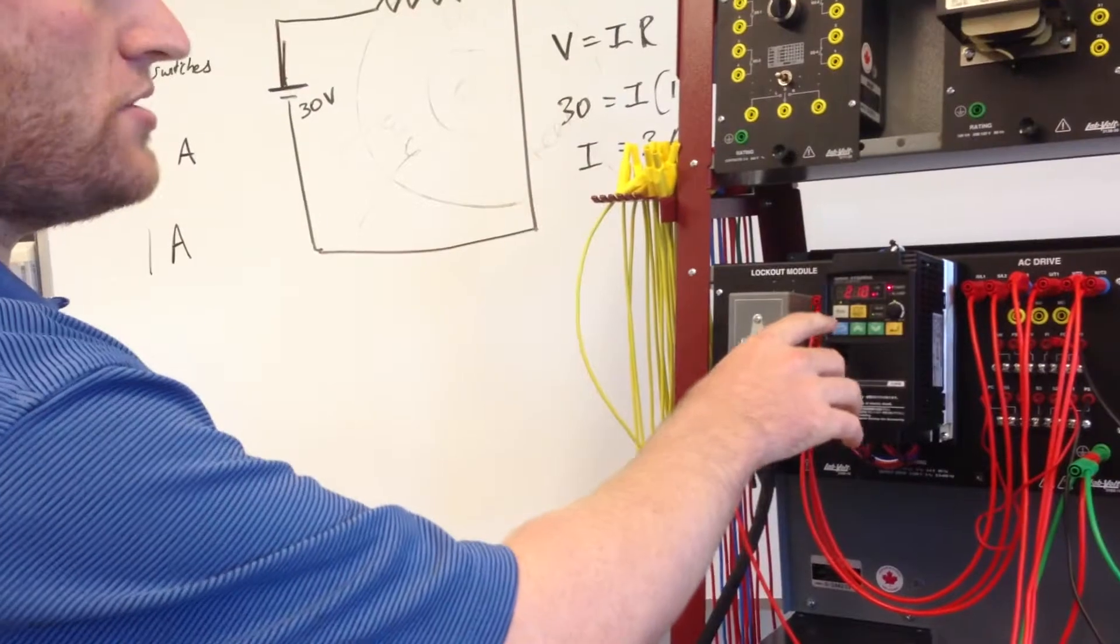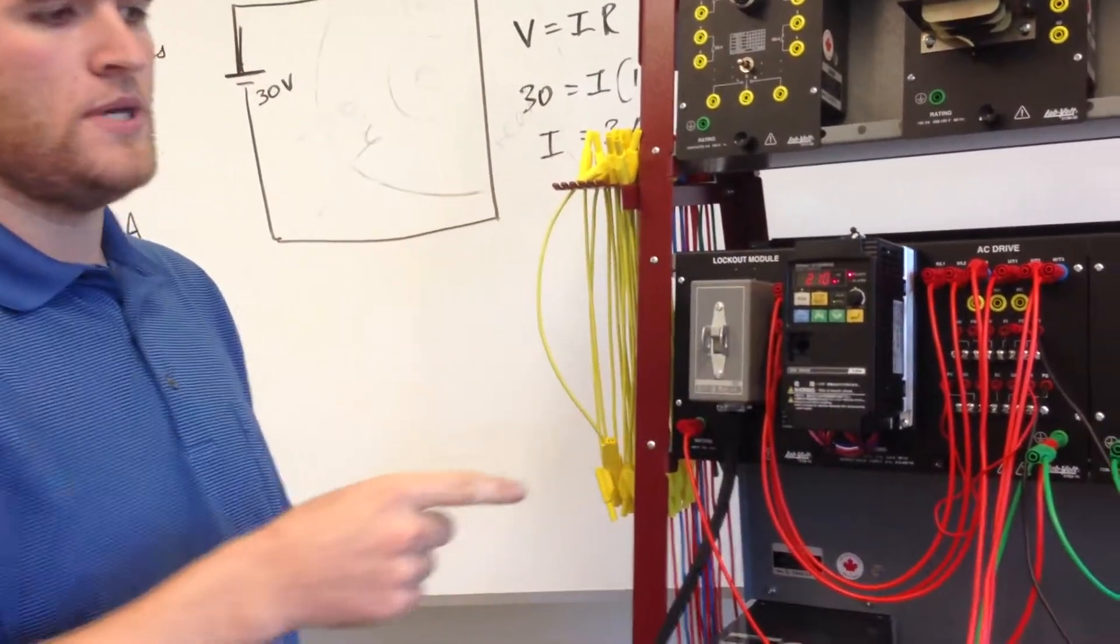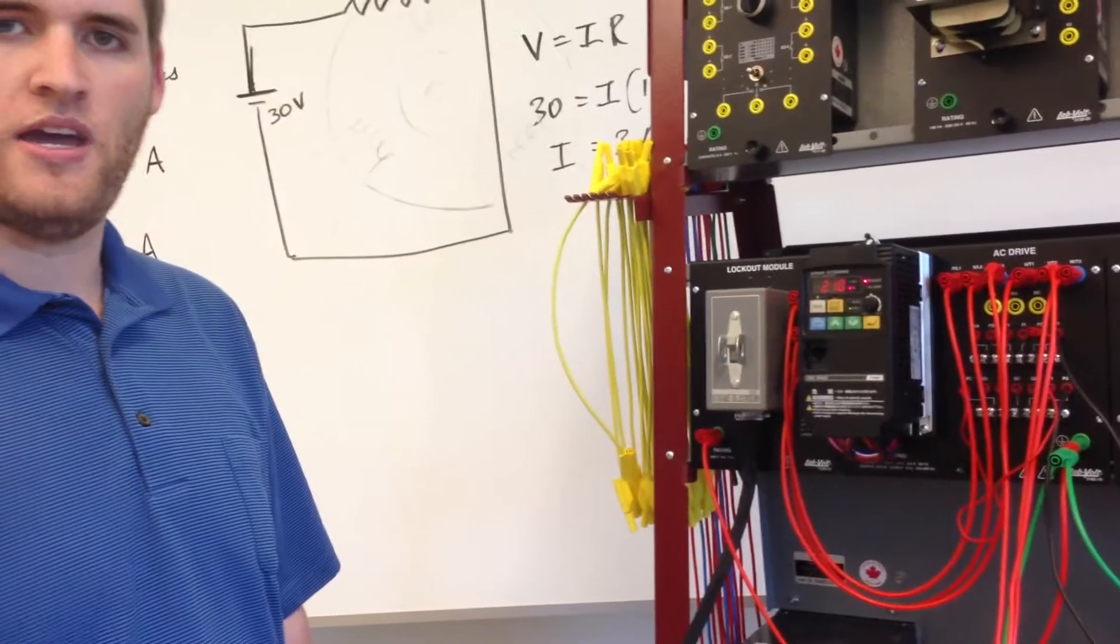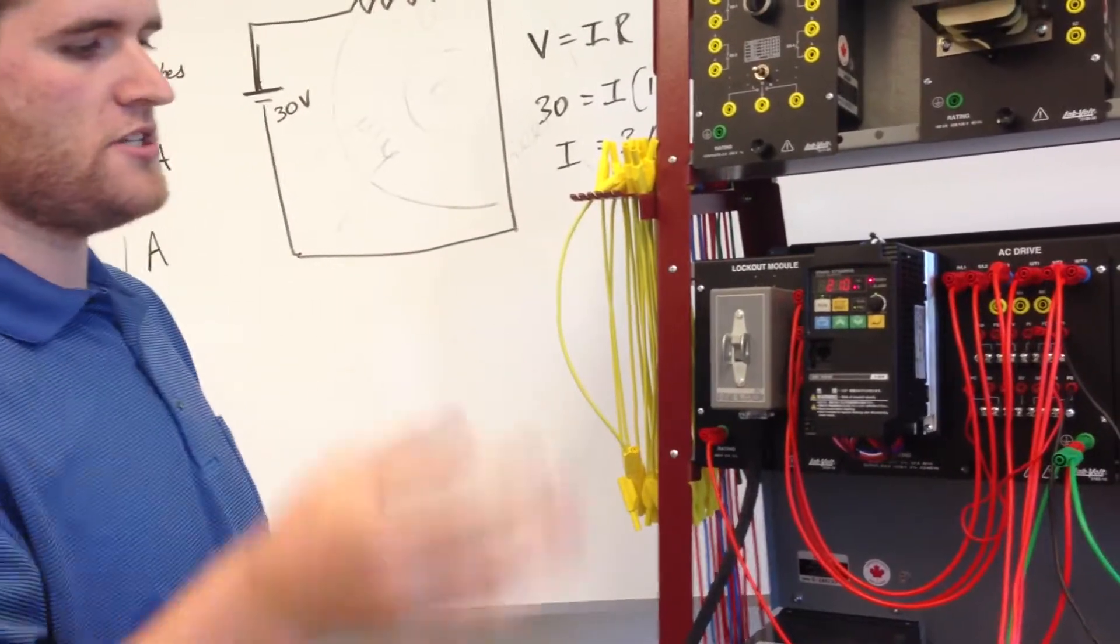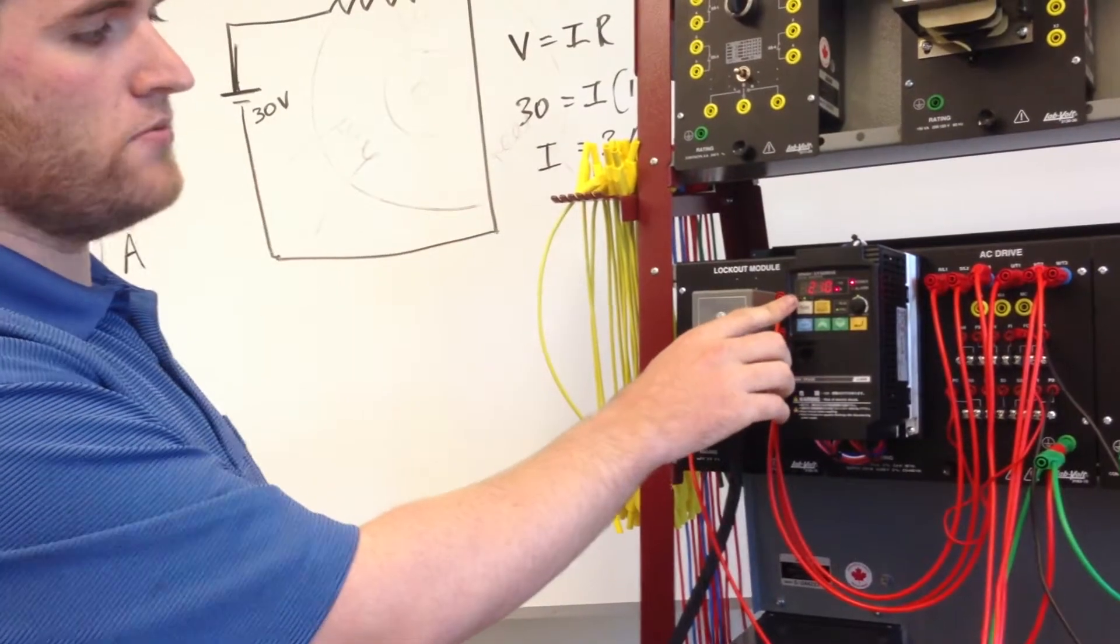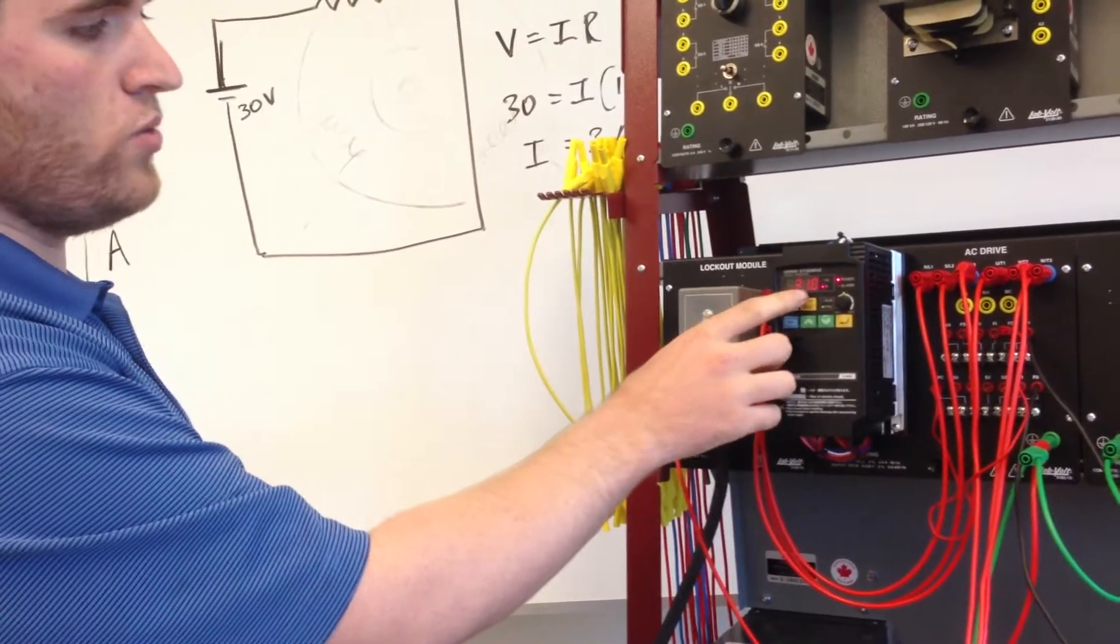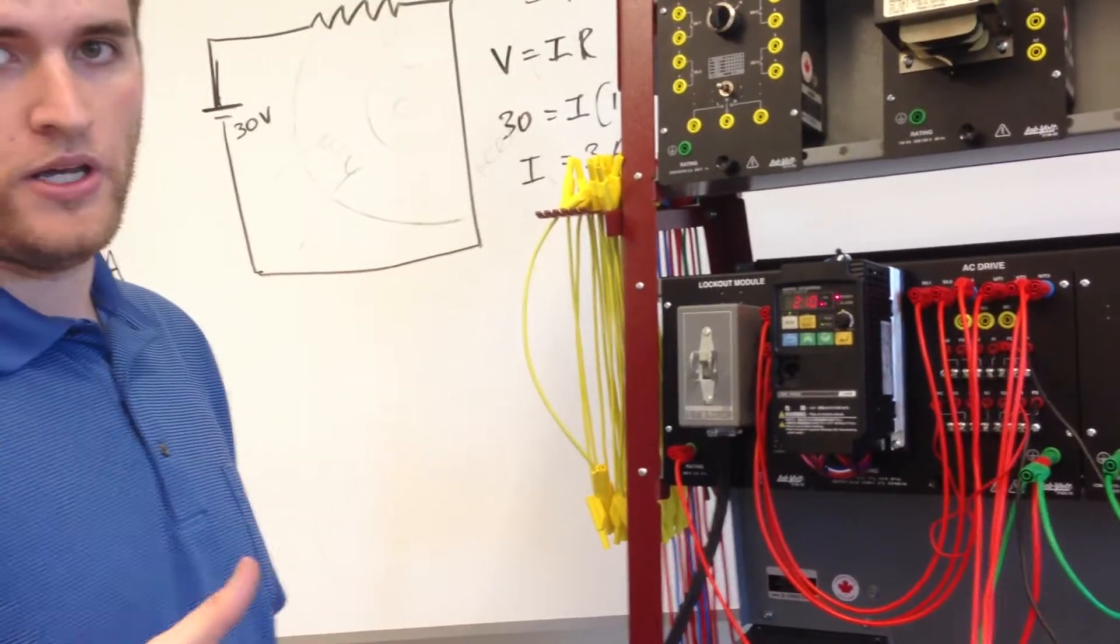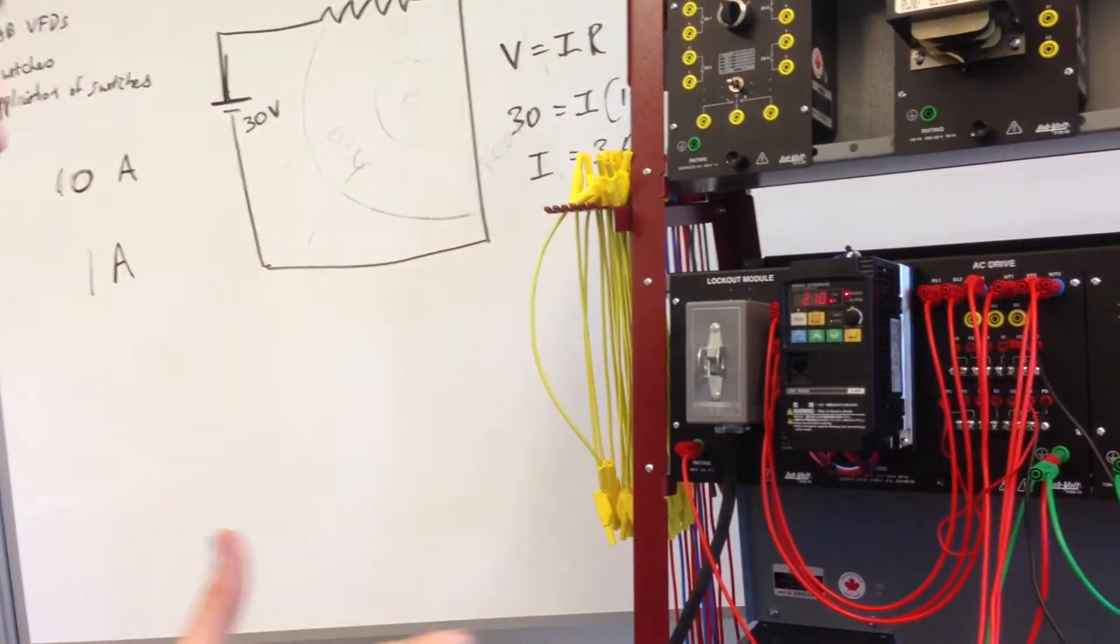What that means is once I turn that load on it's going to go to 2.3 it's going to say okay I'm overloaded and it's going to scale back the motor speed to stay at what my limit is set at. Right now you see it set at 2.1 so that's underneath what my amperage is going to be running so we're going to go ahead and trip that overload.